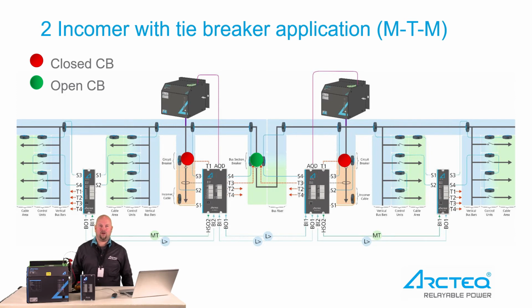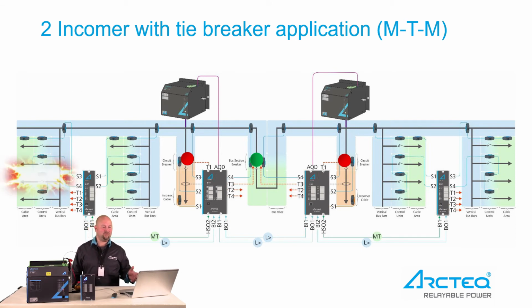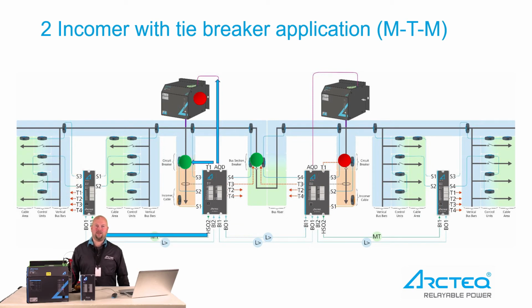And here a short example, let's consider this main-tie-main case. During the test, of course, it is important to test that the correct AQD device is closing. So if we have a fault here on the left side, in this case we should not activate the right hand side quenching device, but we should trip and activate the left side quenching device, and then the fault disappears where the fault started.